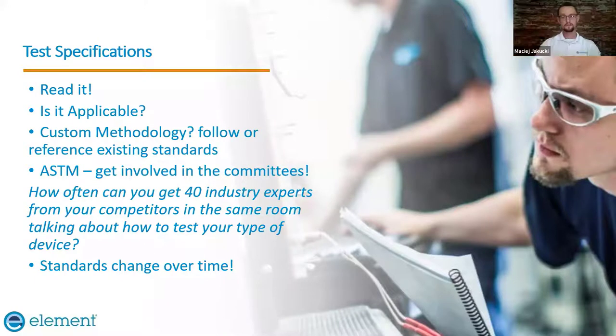Please proceed. So let's see, where was I at here? The specifications typically are defined for a type of implant, but then inevitably you get into custom methodology, taking a look at, let's say, your device has some new locking feature that either hasn't been seen before or falls outside of the standard. What I typically recommend is, if you can identify that as a potential risk the FDA might ask about, or something you have to prove - like your screw is not going to back out or create some adverse risk - identify a similar ASTM test method and build off of that.